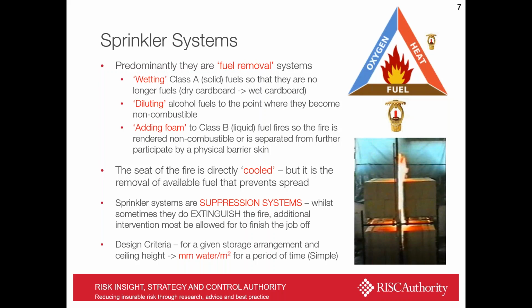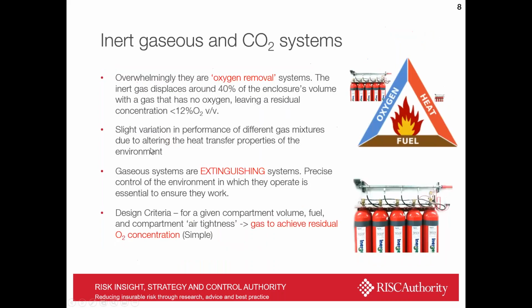Now, the design criteria for sprinkler systems is a very simple one. Essentially, at the end of the day, for a particular type of storage arrangement and ceiling height, it gets described as millimeters of water landing on the ground per square meter, a very simple design criteria. If we look at the equivalent for gaseous systems or inert gas type systems, these are oxygen removal type systems, where the inert gas displaces around 40% of the enclosure's volume, leaving a residual oxygen concentration that doesn't sustain combustion. And for typical sorts of fuels, that will be somewhere around 12% of oxygen and below.